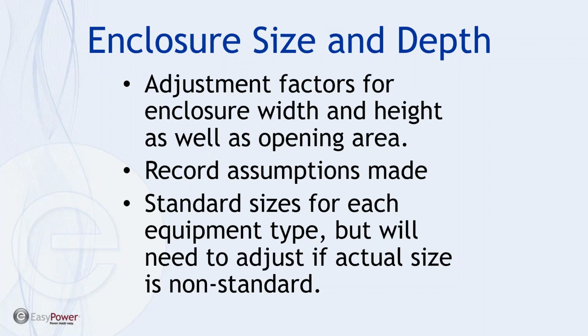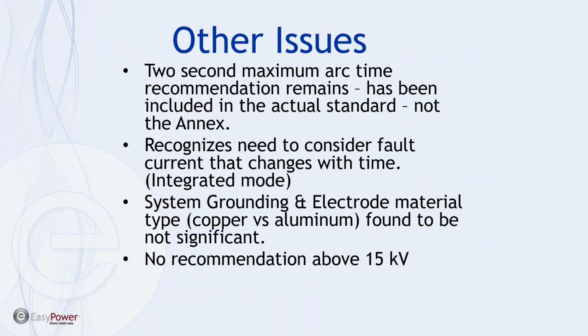What we're going to find when we get into analysis is that the adjustment factor for enclosure width and height actually makes a difference in the calculations, as well as the depth of the enclosure. And while the tools include a standard dimension as recommended by the IEEE model, it's up to us to determine, as we're doing the collection, how much we differ from the standard dimensions.